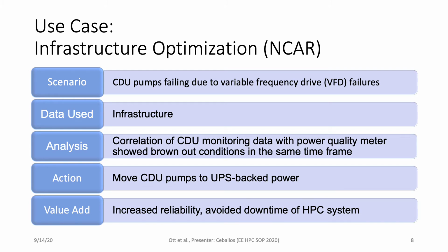They make use of the aggregated data from their site-wide electrical systems, facility mechanical systems, and HPC system cooling distribution units. This particular use case describes a power quality problem that was resolved using their extensive ODA capabilities. During small brownout conditions, they found that their HPC system would not go offline, but the variable frequency drive of the CDU pumps would fail and trigger a turnover between the 2 redundant pumps in the CDUs. This failure would occasionally cause overtemperature conditions in the HPC system's secondary cooling loop.